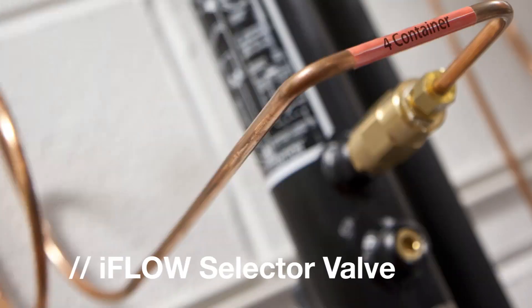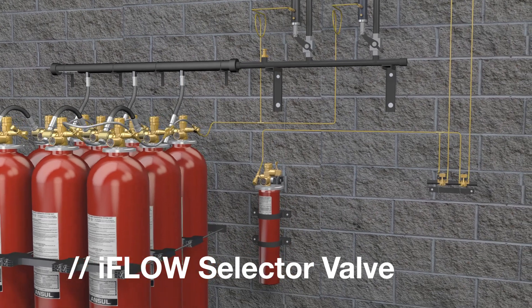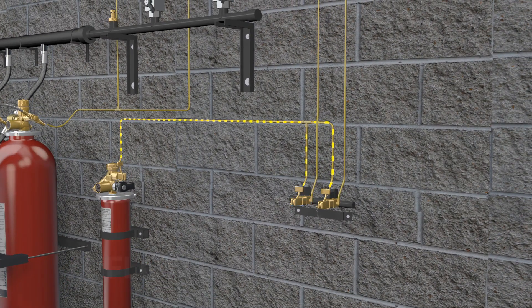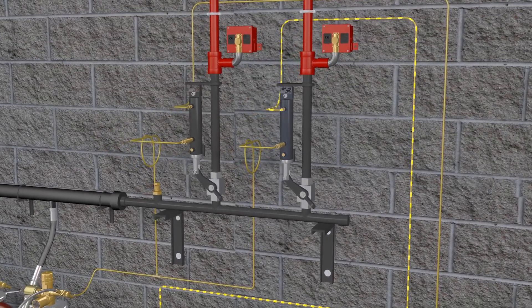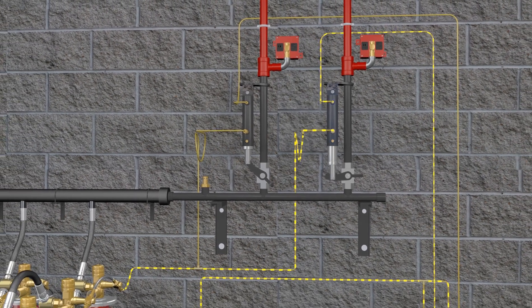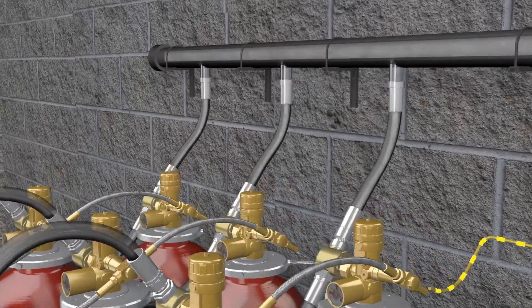Inergen systems are often configured to protect multiple areas with only one container bank to protect the largest volume. The iFlow system offers both an intelligent and economical approach to safety. The selector valve enables gas to be directed to the appropriate hazard. When the system is initiated, the pilot container activates and the solenoid control valves release pressure, which then builds and pushes down on the piston within the selector valves. The lever is pushed down and allows pressure to flow through and activate the container bank.